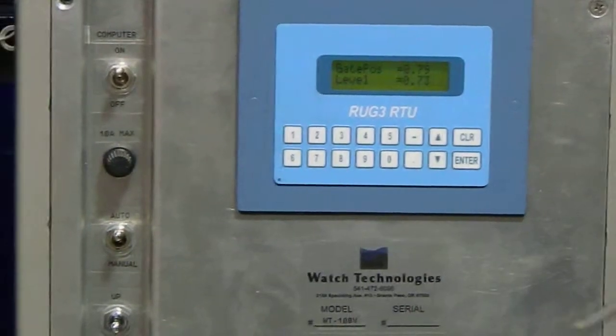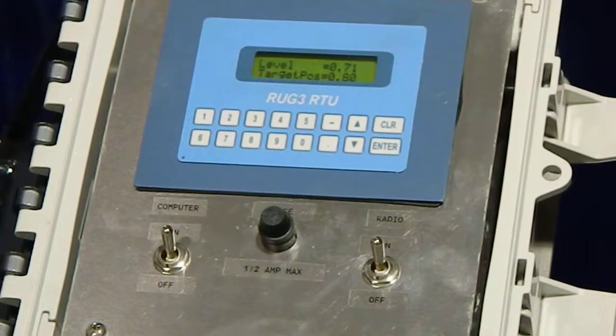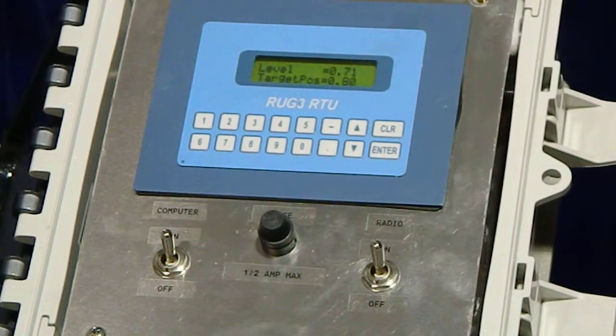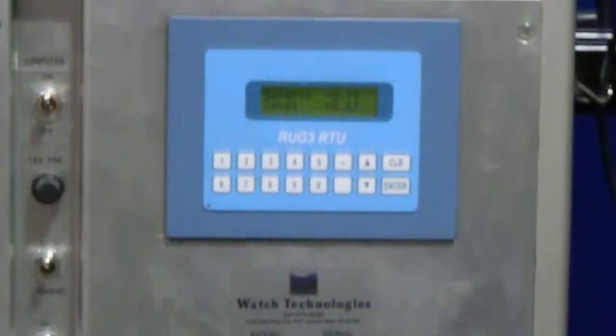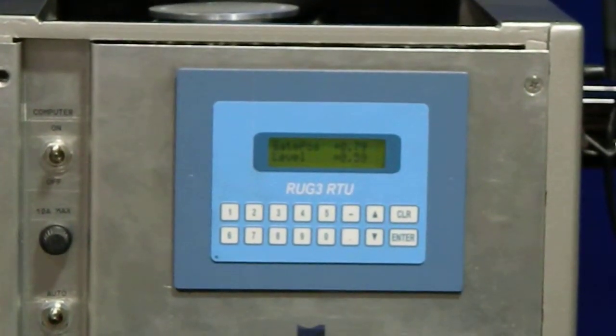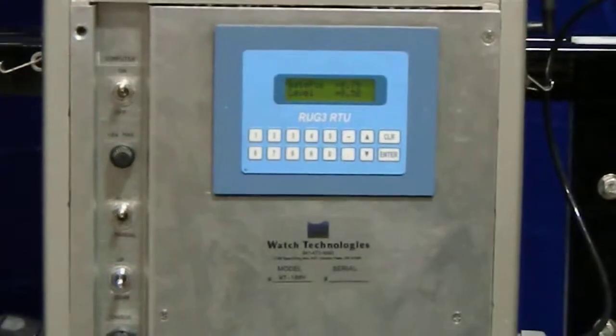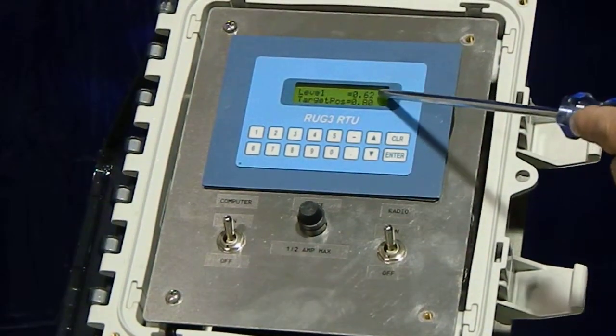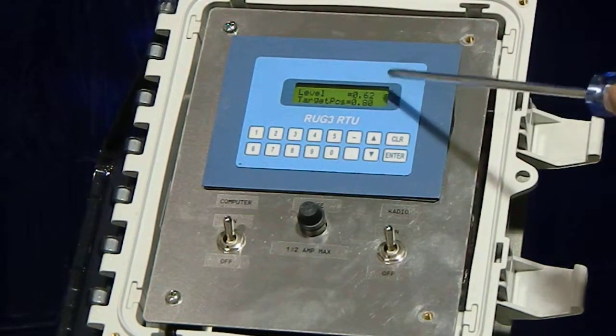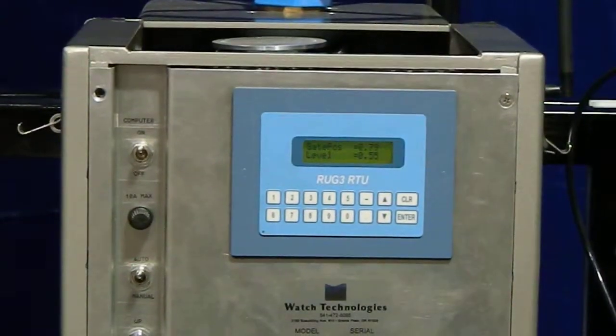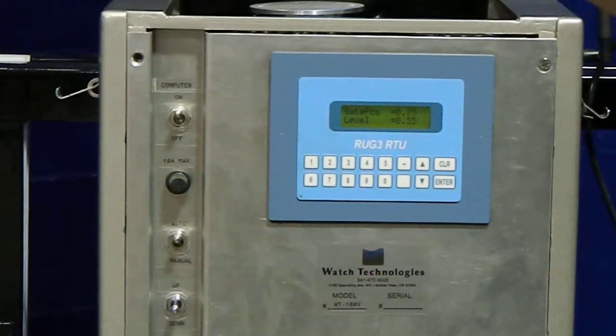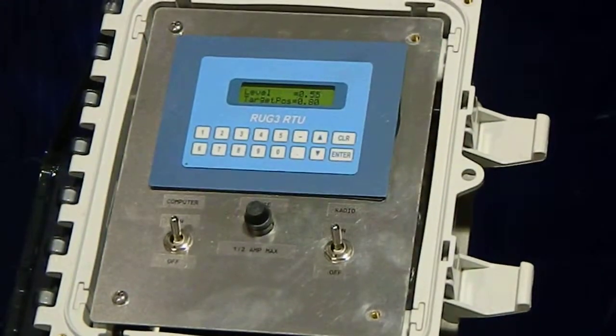And that number, when this one sees change in the remote RTUs, it broadcasts that change to the master RTU, which we'll look at in a moment. But this is settling in at about 0.62. What we can do is take a look over here, and there it is. It's reflecting over here, 0.62 now. Although this lags behind a few seconds, because it doesn't have continuous reading. It's meant to change on this. It's broadcast on change, so you're going to see a little bit of lag time there. Down to 56 now, 55. They're both pretty much in compliance with each other.